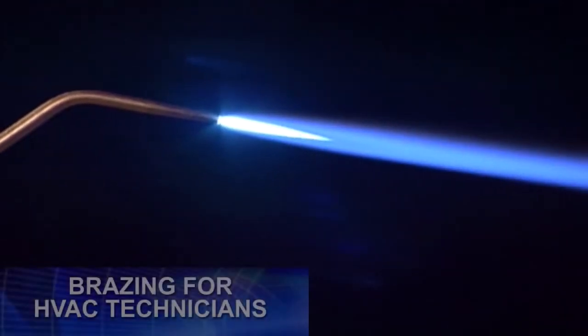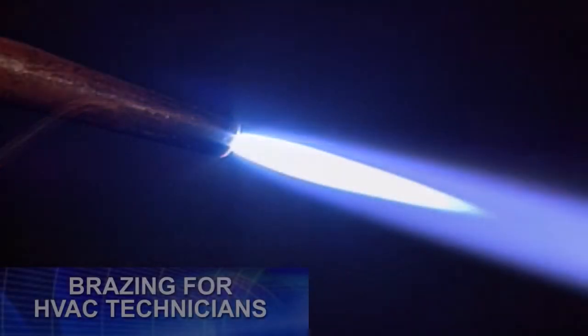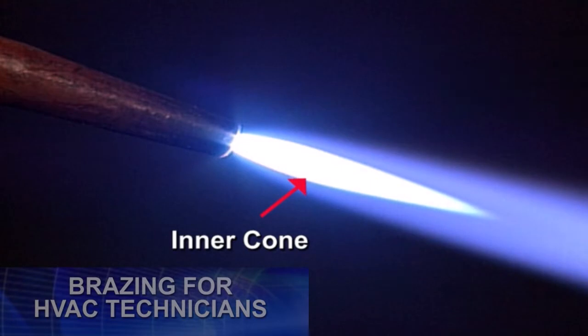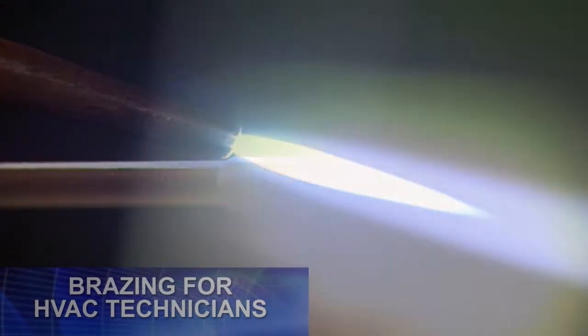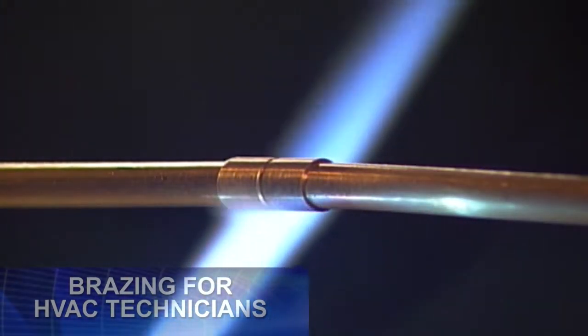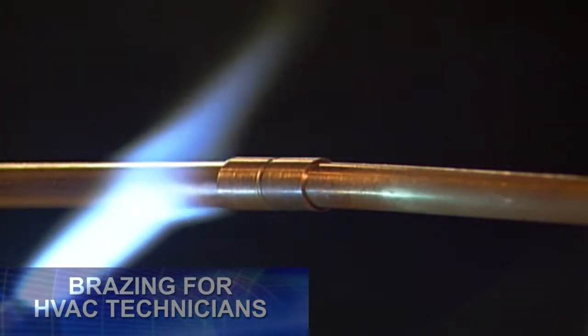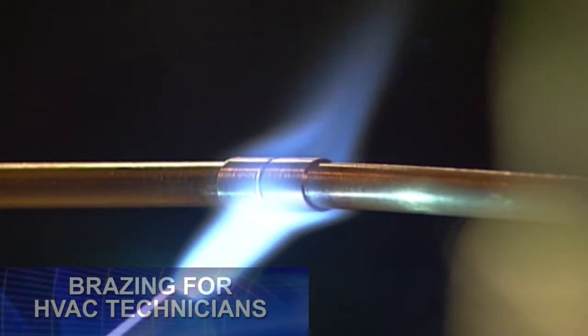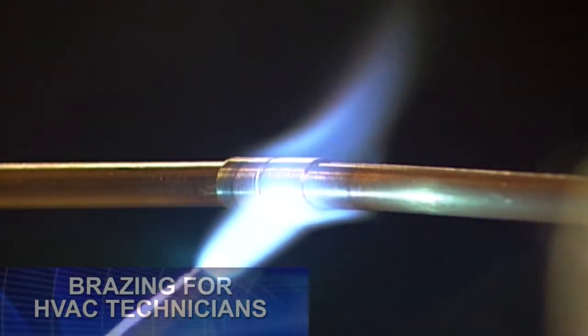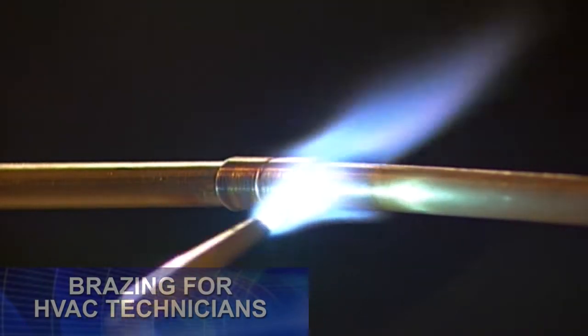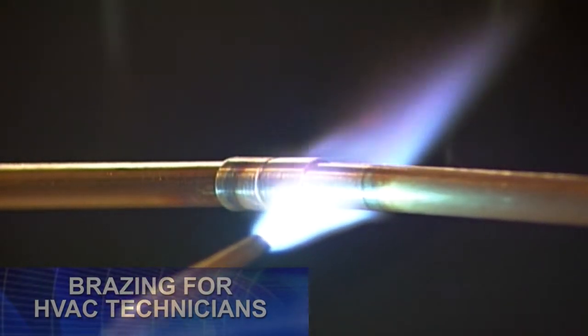Once a neutral flame appears, stop increasing the oxygen flow. A neutral flame has a single inner cone approximately 3/4 of an inch in length. Higher pressure setups have a slightly longer inner cone. A flame that is properly set up for the work to be done is large enough to wrap around the tubing and fitting of the joint. The flame setup is complete and the rig is ready for the actual brazing operation.